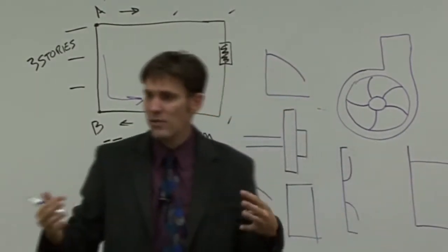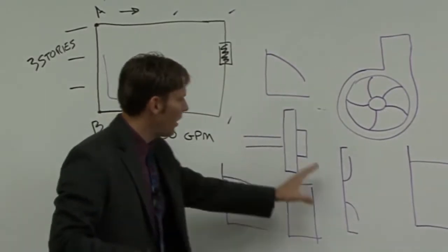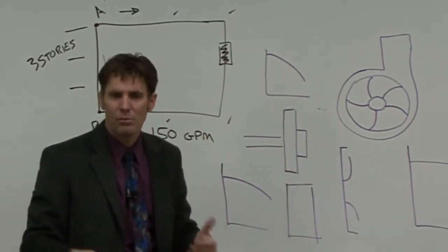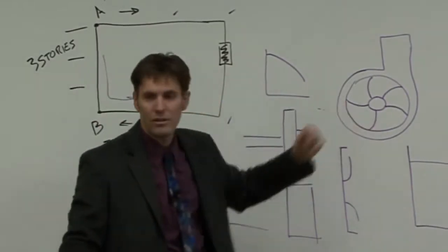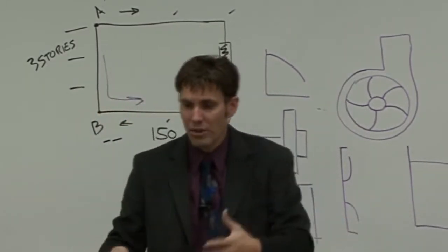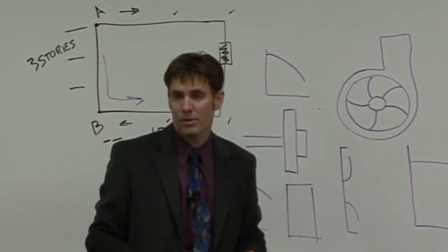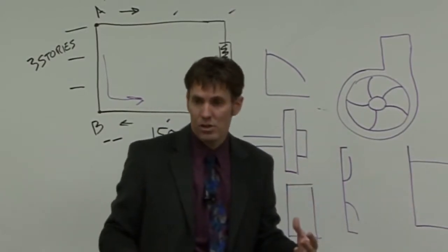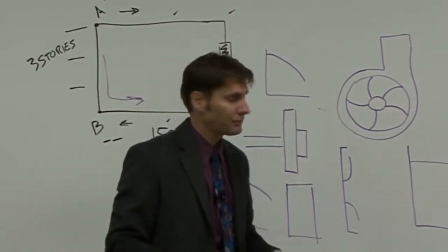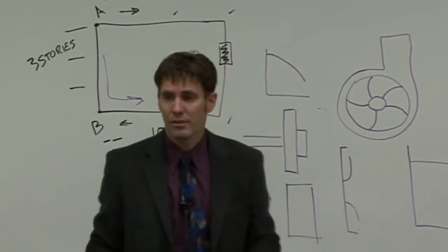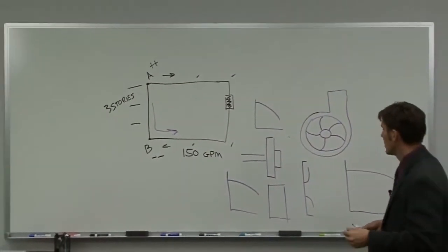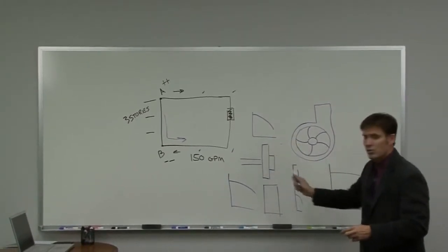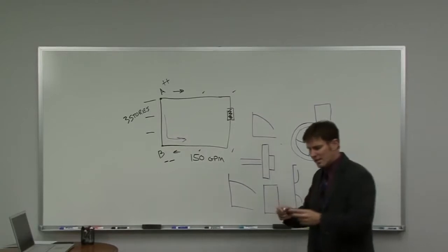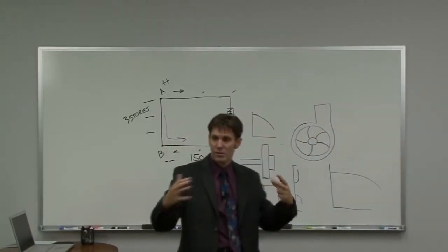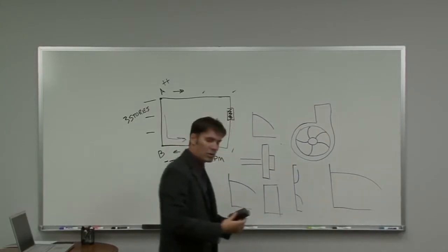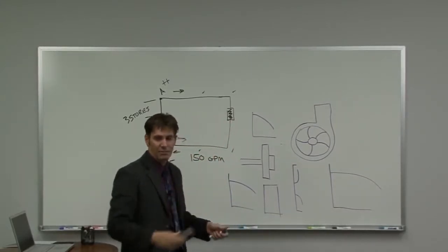So all of your commercial HVAC pump manufacturers will have pumps that look fairly similar in their curves. Some will be more efficient than others because they've spent more time in their R&D. In my personal experience of working with the different pump curves, I have been very impressed with the Patterson pump curves. They seem to be very efficient, a lot of times more so than the competition, and they really know what they're doing. So you've got some good product that you're using. But this is, again, what defines these pump curves. So now let's clean this up, and we'll start diving into more of the actual pump curve, how to read it, and how to understand everything that's taking place on that pump curve.